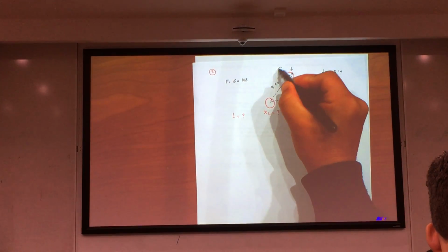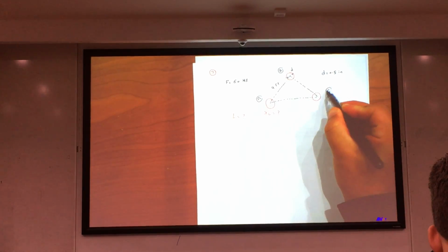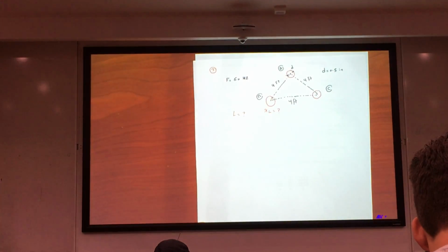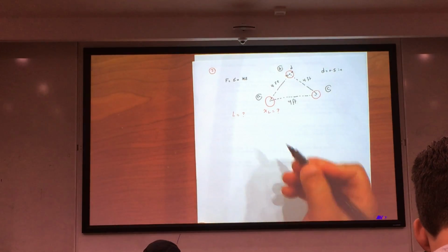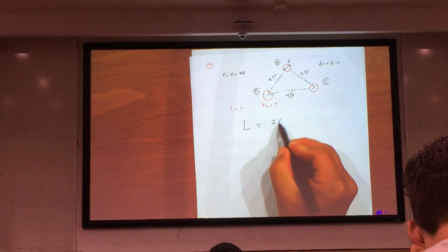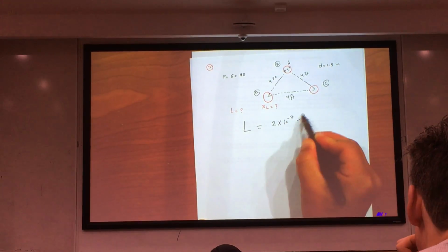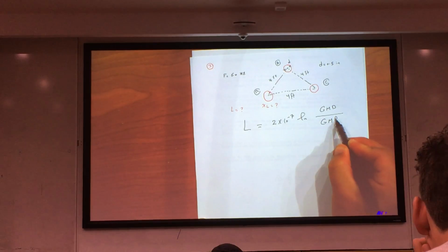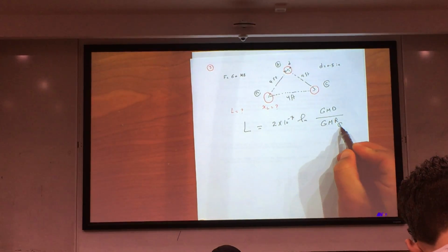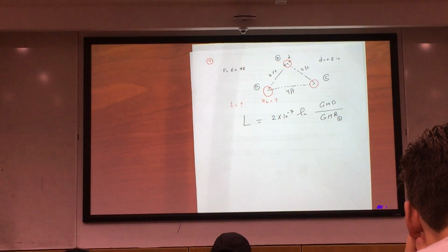So you have all the information to calculate this. Because the inductance for any phase, phase A, phase B, and phase C, and the distance here is 4 feet in each. So again, the general formula for L, very easy to remember: L for any phase is equal to 2 times 10 to the power minus 7 times ln of geometrical mean distance divided by geometrical mean radius. Always reminding you, for this L, the geometrical mean radius for L calculation is different than for C.